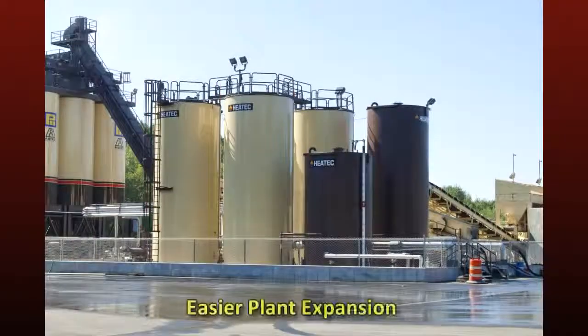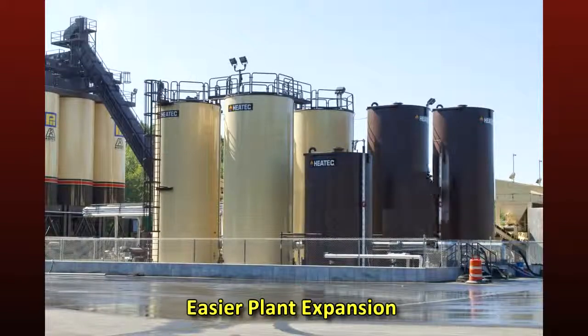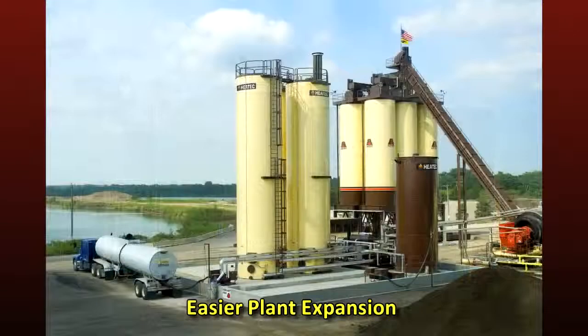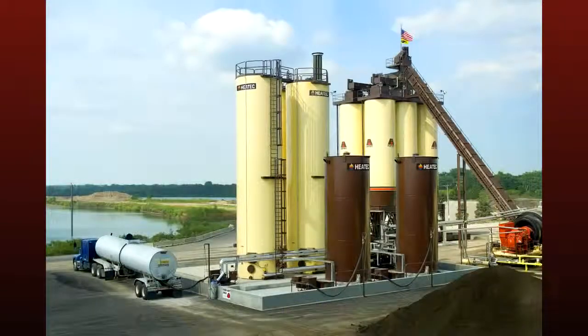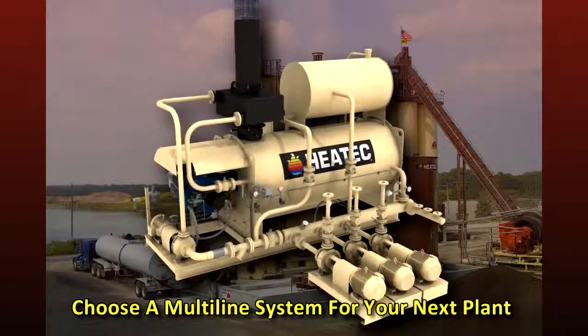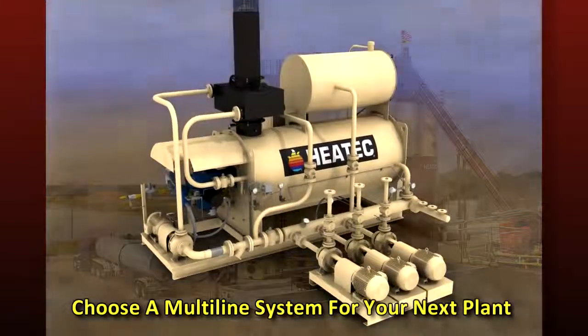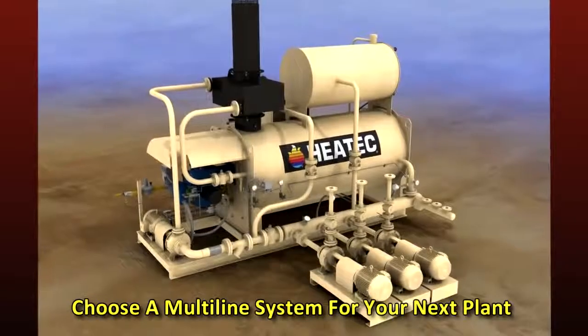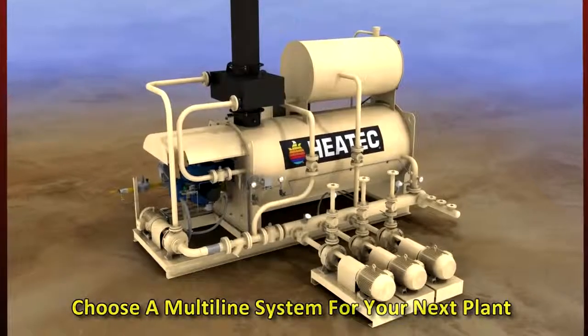A multi-line heating system also facilitates adding tanks and other components to an existing hot oil system. So we strongly recommend the multi-line system with a manifold heater over a single-line system for most HMA plants.